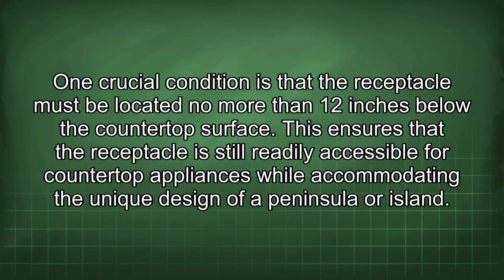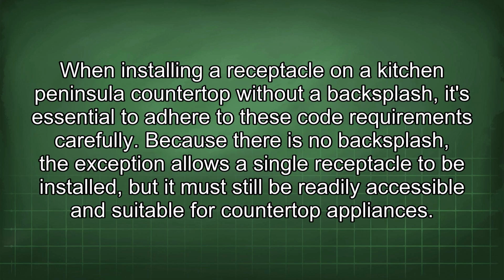or island. When installing a receptacle on a kitchen peninsula countertop without a backsplash, it's essential to adhere to these code requirements carefully. Because there is no backsplash, the exception allows a single receptacle to be installed, but it must still be readily accessible and suitable for countertop appliances.